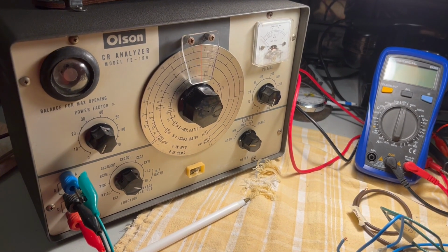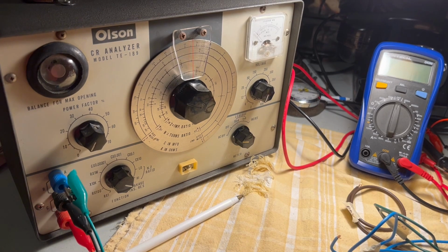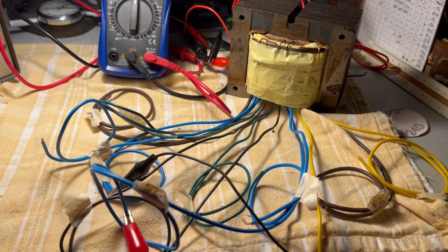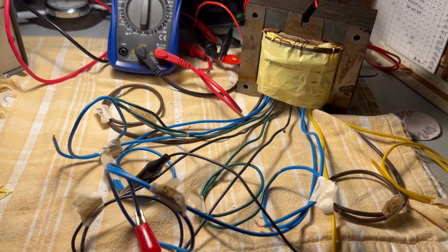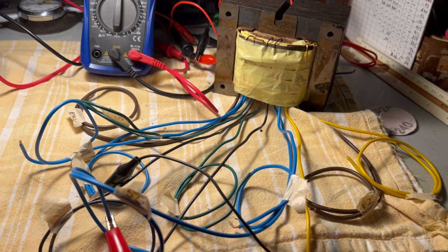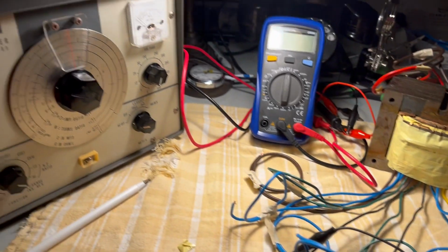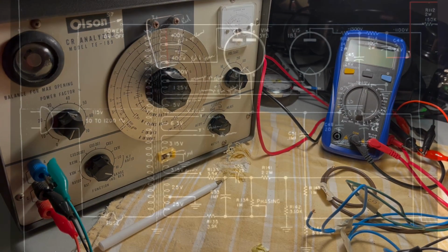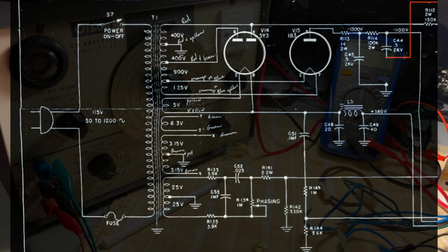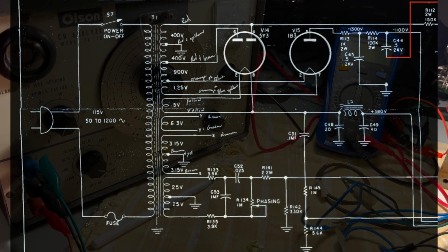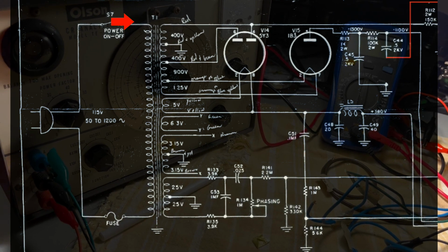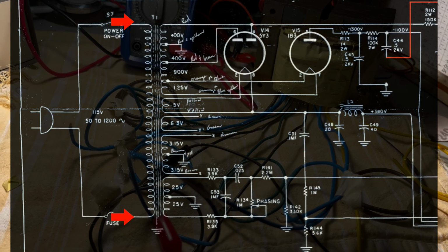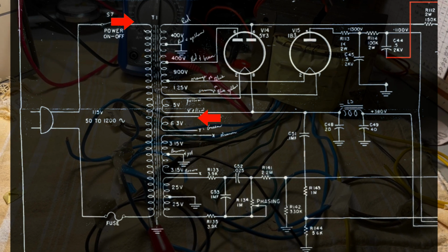Excuse me. Now I think what I want to do is go through with my turn ratio analyzer and just verify that the turn ratio and everything is running in the direction that I think it's supposed to be running. I need to verify all of that before I get down to wiring it. And what I mean by that is that if I can superimpose the drawing on top and I make the assumption, just for a language to choose, that the top of the coil would be the positive end and the bottom of the coil would be the negative end, I want to make sure that the top of all of the secondaries is on the same end as it is on the primaries.